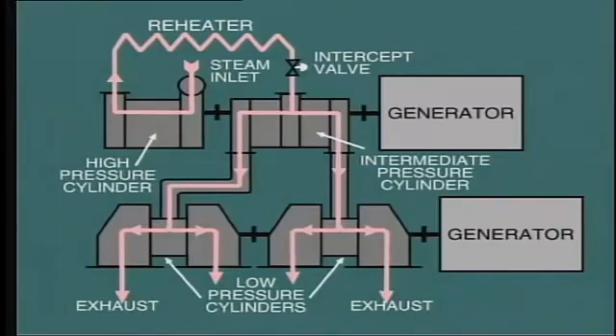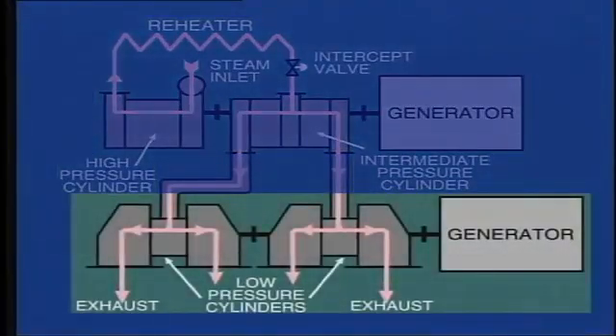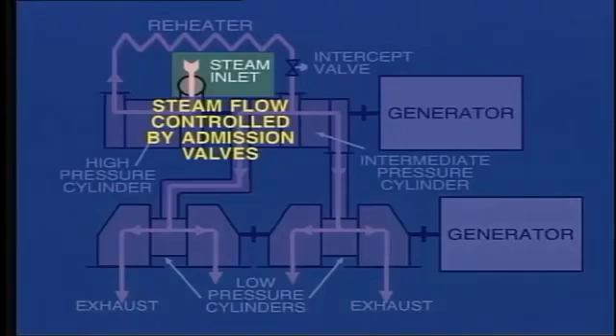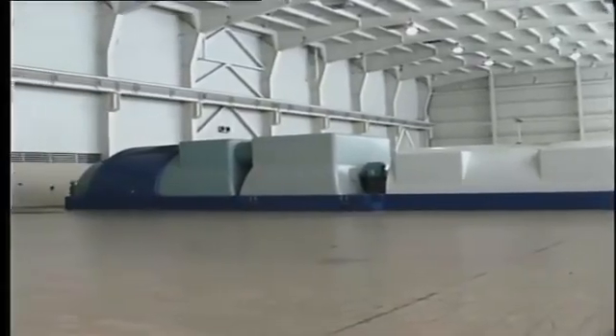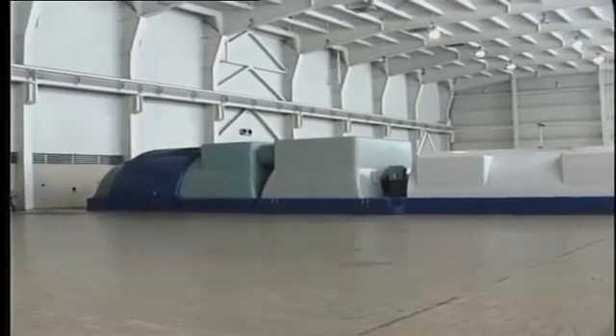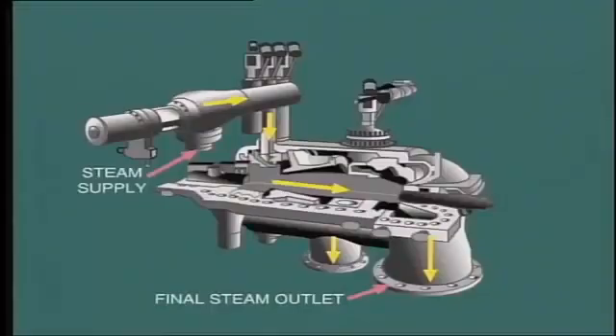Yet another cylinder arrangement used on earlier reheat machines is known as the cross-compound system. It consists of two separate turbines, each coupled to their own generator, but interlocked through a common steam system. The high-pressure and intermediate pressure cylinders drive one generator, while the two low-pressure cylinders drive the other. The steam flow through the combined turbine is controlled at the high-pressure inlet, thus controlling the output of both generators. More recent installations, particularly in industrial situations, are likely to be smaller units, probably within the range of 60 to 150 megawatts.